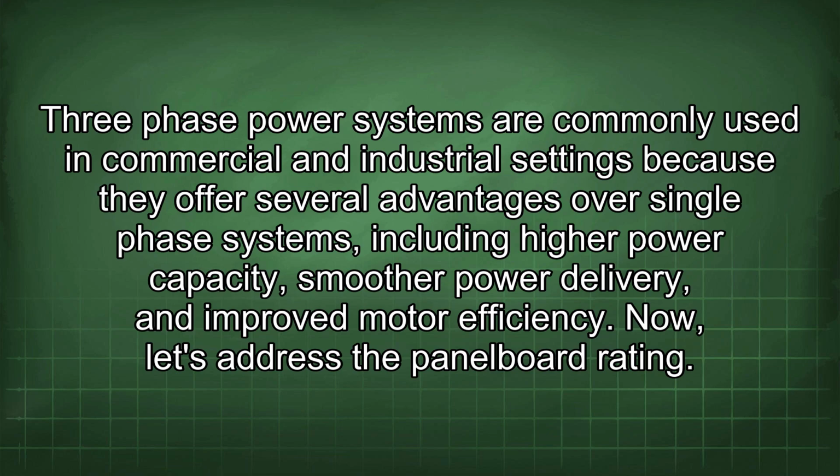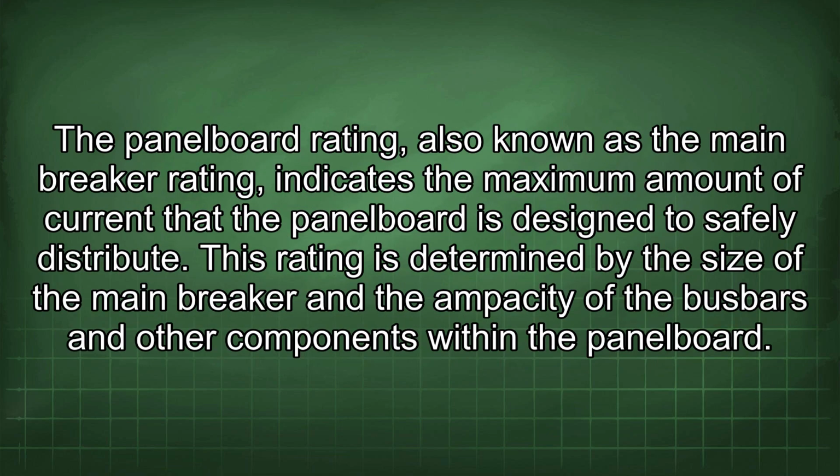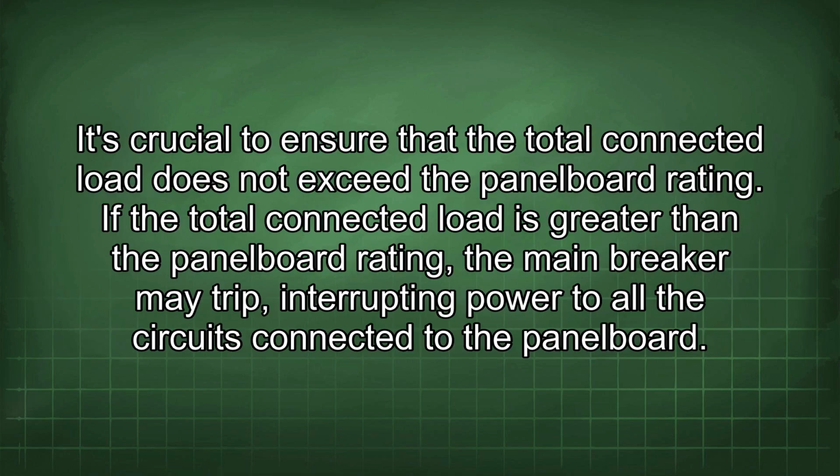Now, let's address the panel board rating. The panel board rating, also known as the main breaker rating, indicates the maximum amount of current that the panel board is designed to safely distribute. This rating is determined by the size of the main breaker and the ampacity of the busbars and other components within the panel board. It's crucial to ensure that the total connected load does not exceed the panel board rating.